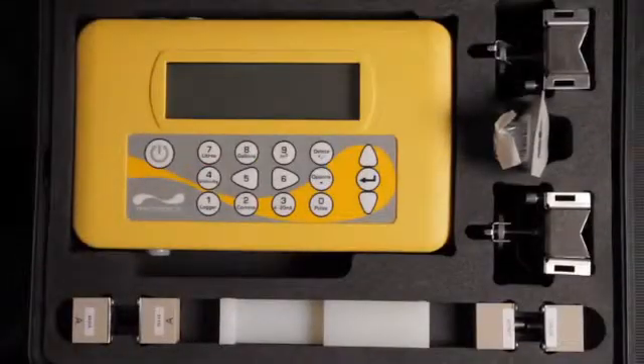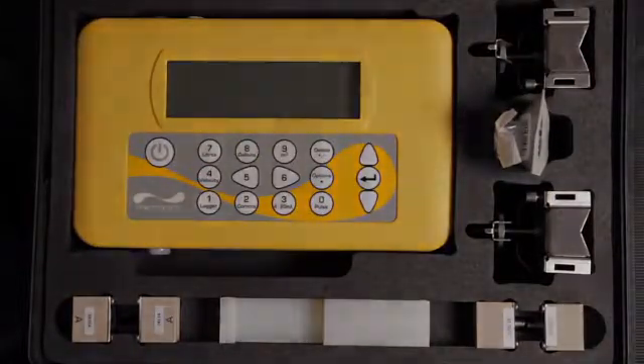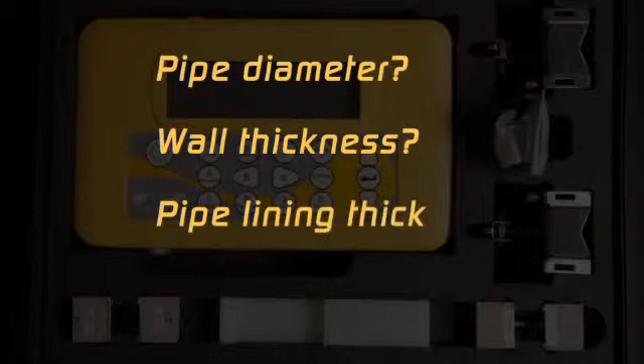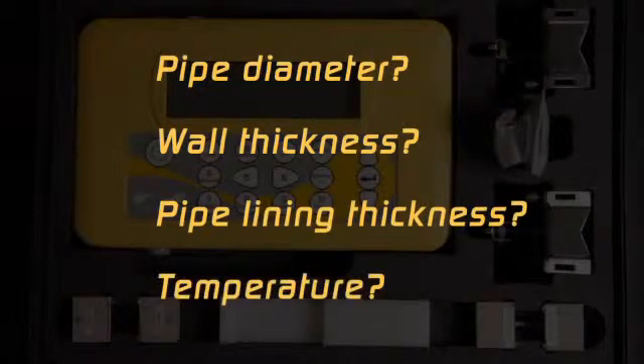First steps begin with how to program the flow meter. When programming the unit you need to know the pipe outside diameter, the wall thickness, the pipe lining thickness if required, and the temperature of the application.